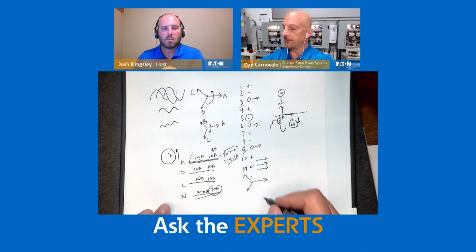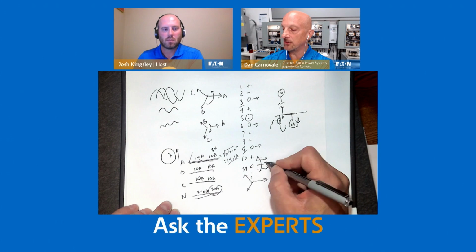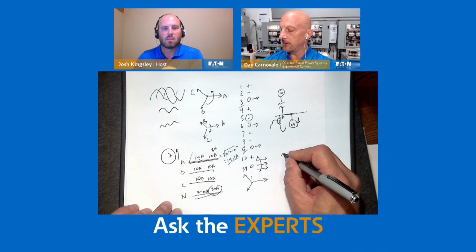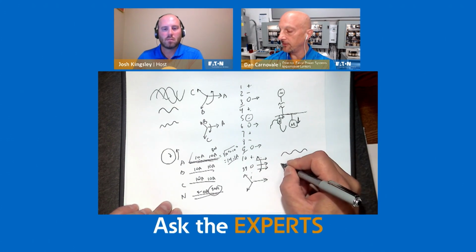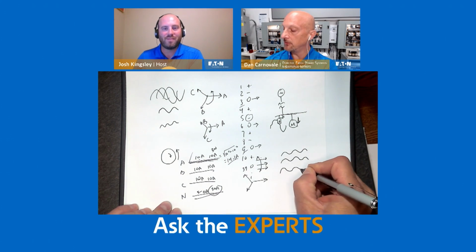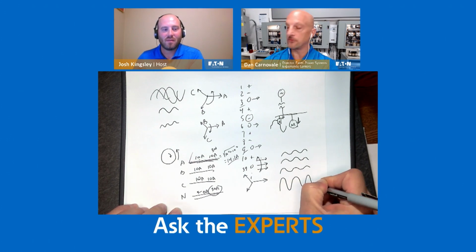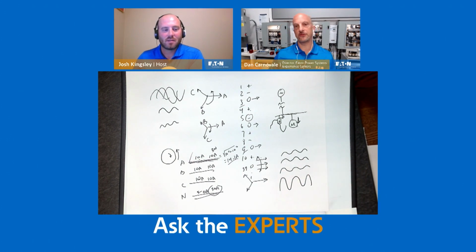And by the way, these also rotate as vectors or phasors, but they rotate together. So when you add them up on the neutral, all three of them add up exactly in phase with each other, if I could draw it correctly. And so what you end up with is three times the current in the neutral. So that whole discussion really goes to the fact that each of the harmonics, or characteristic harmonics, have different patterns to them.